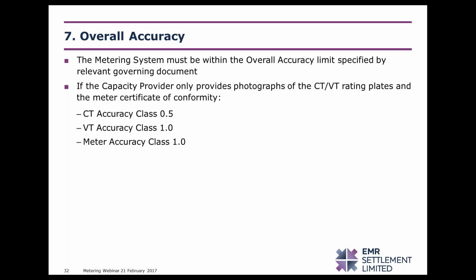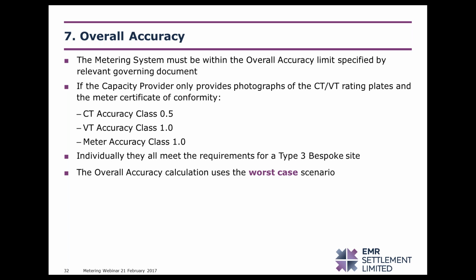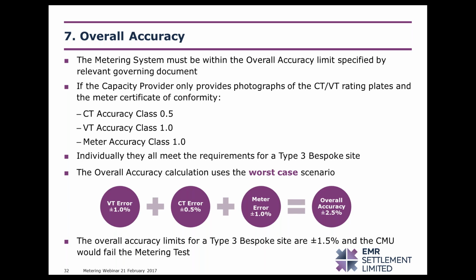So if we take an example where a capacity provider has provided photographs of the measurement transformer rating plates, and this has demonstrated a CT accuracy class of 0.5 and a VT accuracy class of 1, and they've only provided a certificate of conformity for the meter that confirms it is a class 1 meter. If this was used in a type 3 bespoke metering installation, individually each one of these pieces of metering equipment would be compliant with the rules. However, the overall accuracy calculation uses the rated accuracy class, and these are the figures that are used in the overall accuracy calculation.